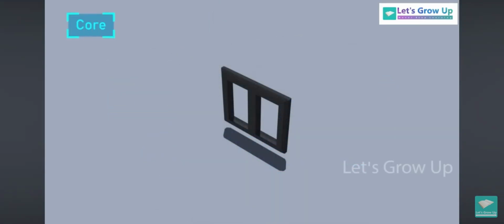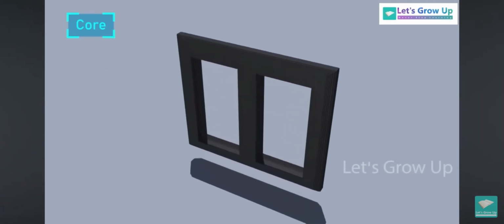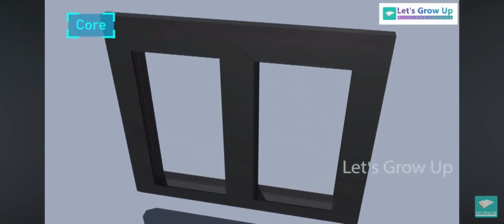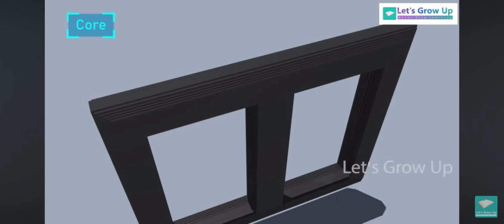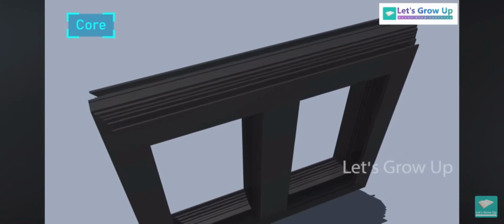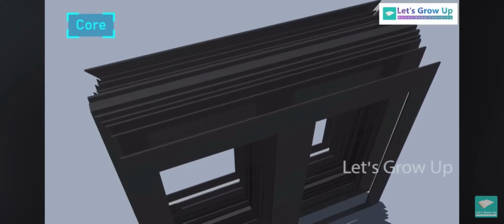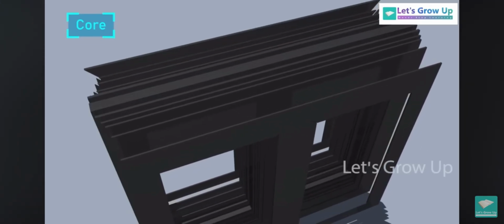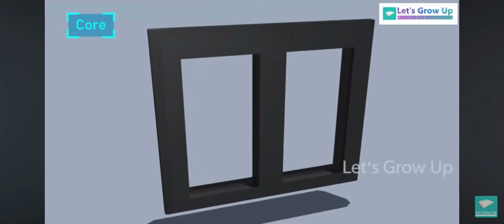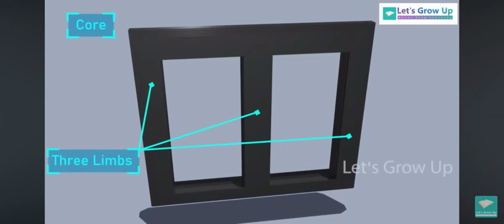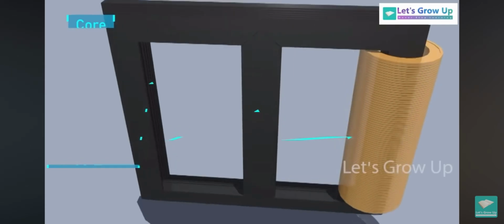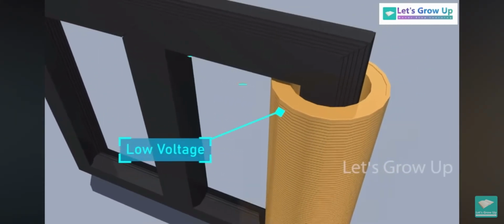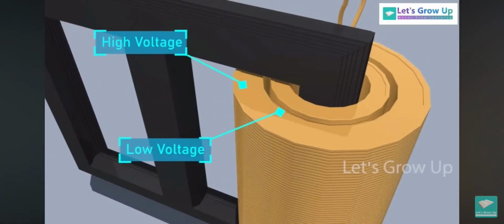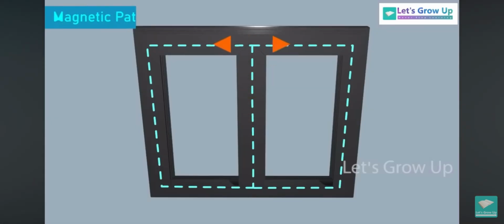So this is the main part of the transformer. It is called the core, or the heart of the transformer. It is made up of iron or silicon steel, or ferromagnetic materials. It is thin metal strips and laminations insulated by a coat of varnish or paper. The core of a three-phase transformer consists of three limbs in the same plane, and each limb carries both low voltage winding and high voltage winding. The core provides a path for the magnetic flux around the core.